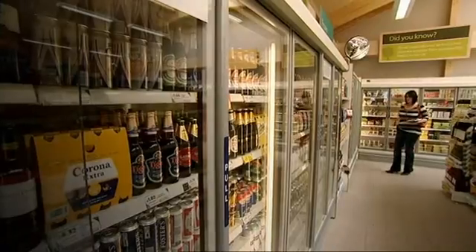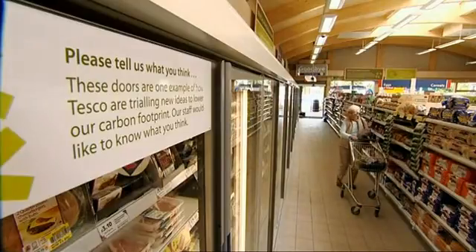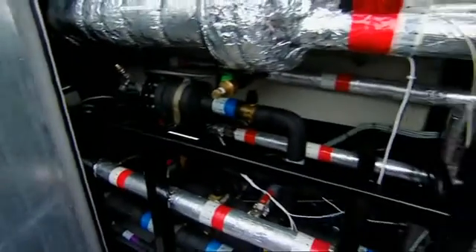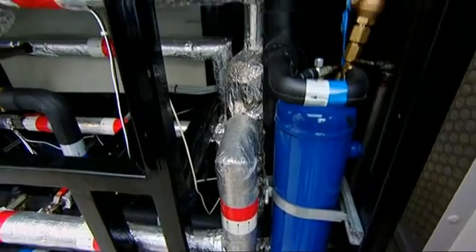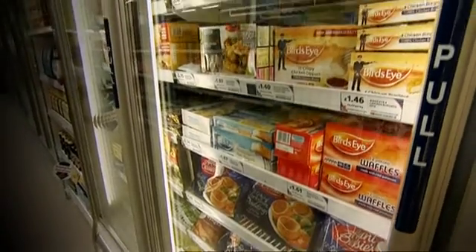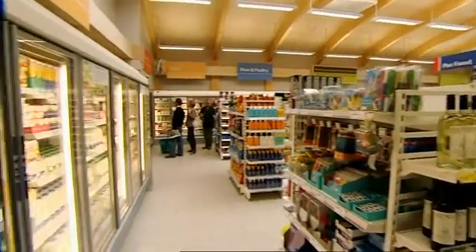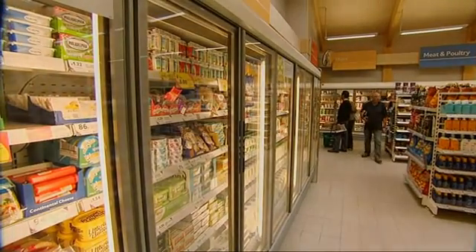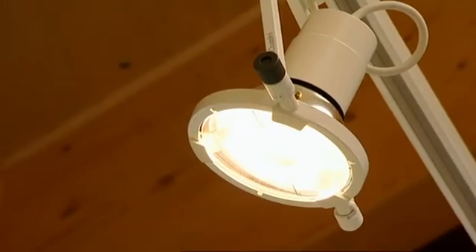We are focusing on what we can do so we can make a difference right now. That's why we're looking at CO2 transcritical refrigeration — this is certainly the first store in the Tesco estate that has that. It produces high-grade waste heat as a by-product of the refrigeration, and we can use that to heat the store. So not only does that give a good environment for customers to shop in, but it saves us using electricity, energy, and gas — reducing kilowatt hours and carbon production on heating the store.